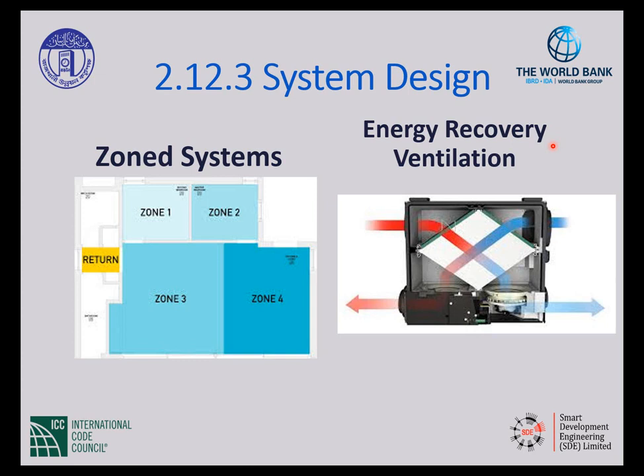When I have to ventilate a building, and a lot of buildings require a lot of ventilation, especially commercial buildings, assemblies, and offices and those kinds of things, they require a lot of fresh air based on how many people are in the building. And so I'm bringing that fresh air into the building, and it's coming in at whatever temperature it is outside. So if it's 100 degrees outside, I'm bringing in 100-degree air, and now my air conditioner has to offset that. Right now it has to work harder. The whole idea here is to keep that equipment from working very hard.